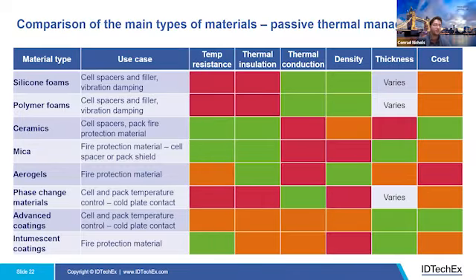When choosing which material to use as a BESS manufacturer, developers must first consider the material application and whether it requires thermally conductive or thermally insulating materials. More thermally conductive materials like polymer foams and phase change materials can be used to aid heat transfer away from the cells and help reduce hotspot formation within the BESS. However, they display low temperature resistance since they are conductive materials compared to others, and so typically do not offer flame retardant barriers or properties.